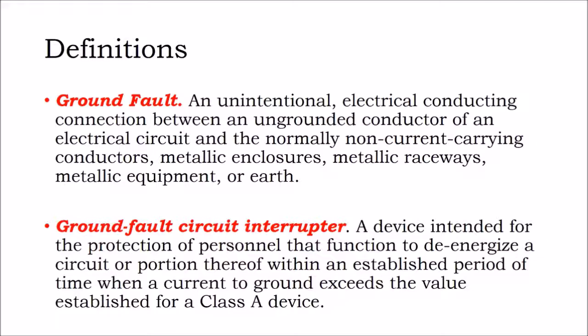And that might sound like, oh no, there's something wrong, and there is. A ground fault that is not planned for nor expected is not a good thing. But what would be worse is for that ground fault not to occur and for that metal box or that metal conduit on the building to be energized, and you go up and touch it and you become the ground path, and that's even worse. When we do have ground faults, we need to have a path to ground for that ground fault to carry over.